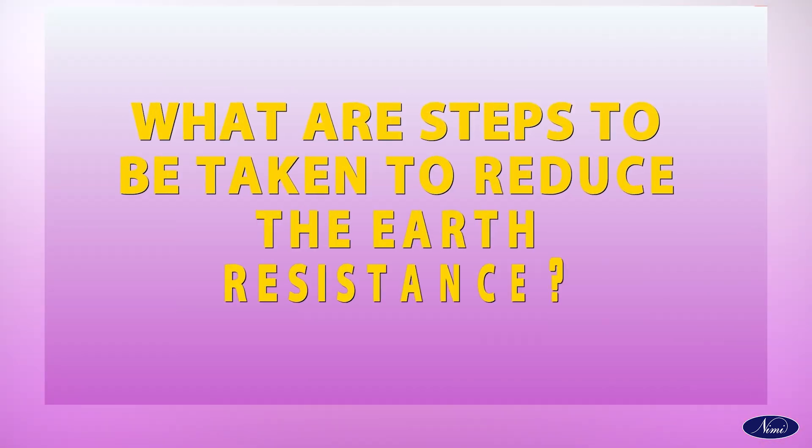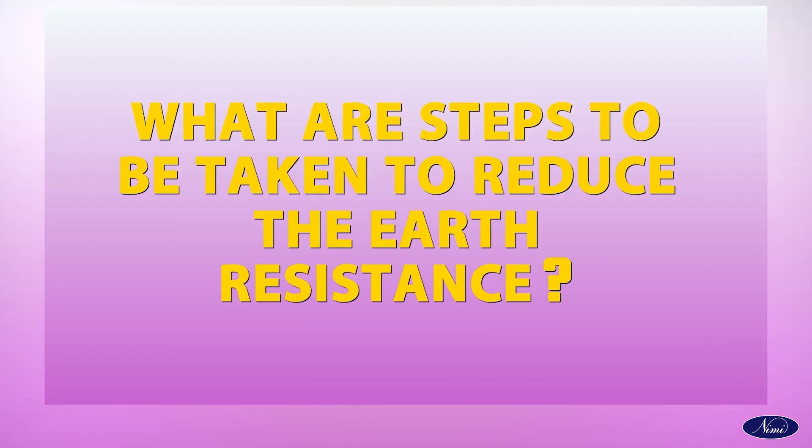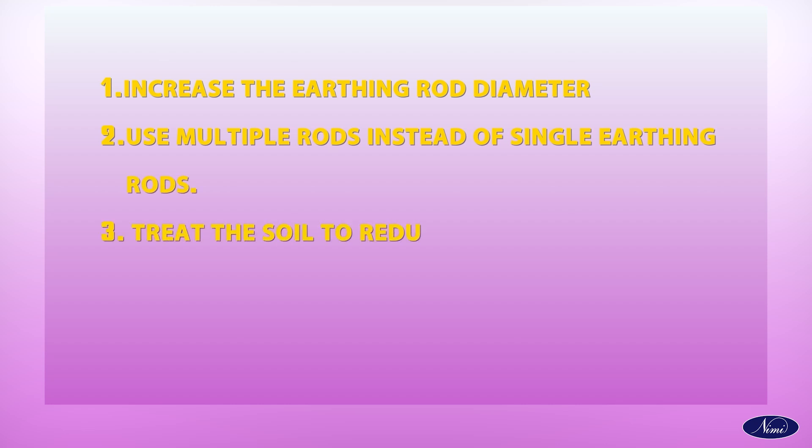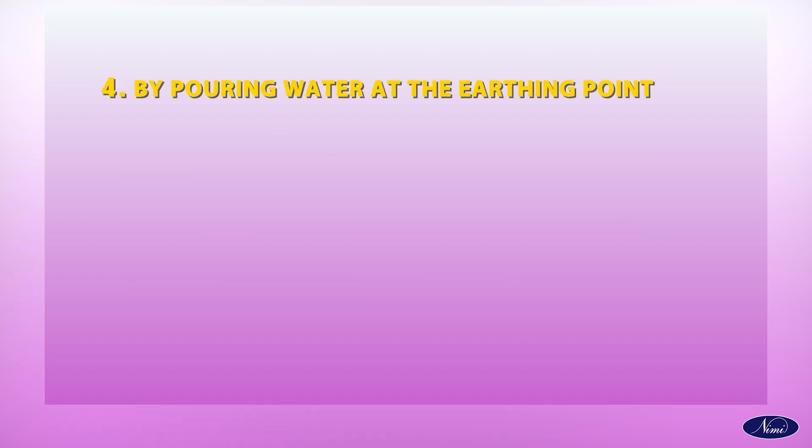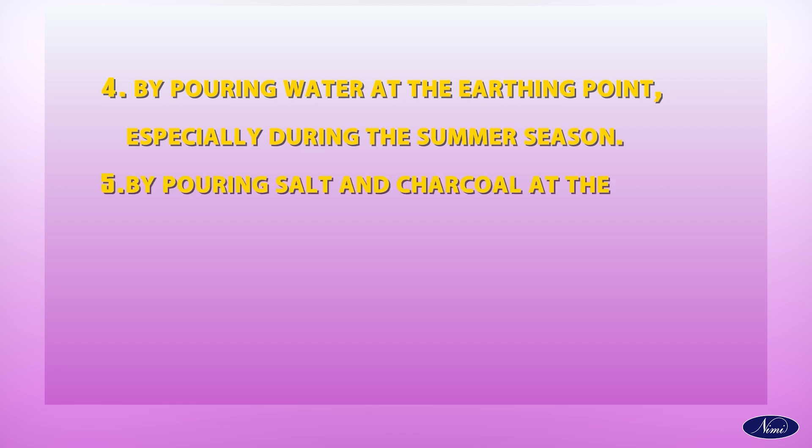What are steps to be taken to reduce earth resistance? Increase the earthing rod diameter. Use multiple rods instead of single earthing rods. Treat the soil to reduce its resistivity by adding chemical compounds. By pouring water at the earthing point, especially during the summer season. By pouring salt and charcoal at the ratio of 1 is to 5. Soldering or welding the nuts and bolts.